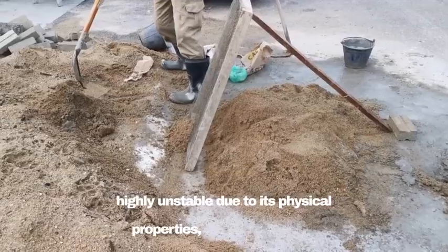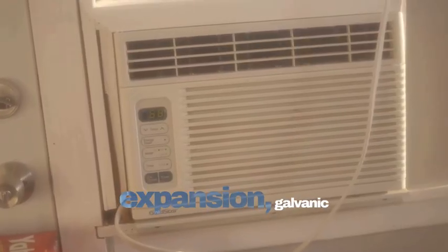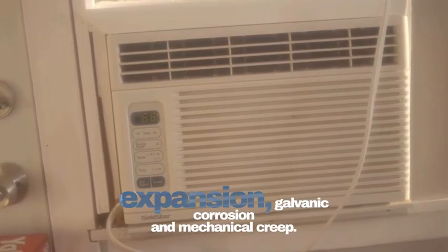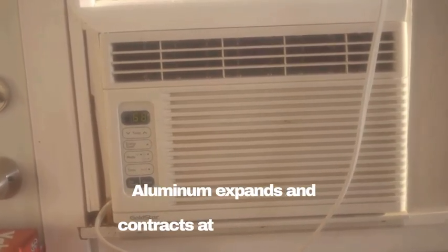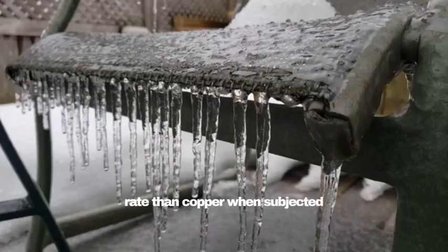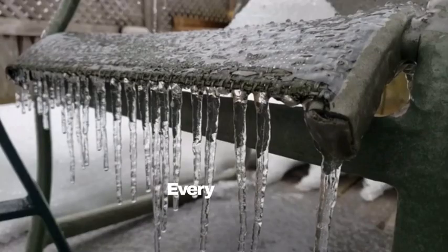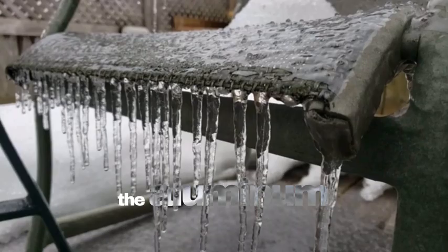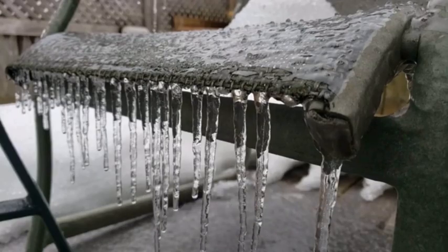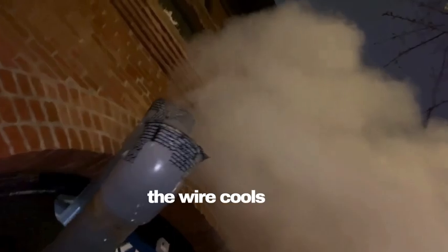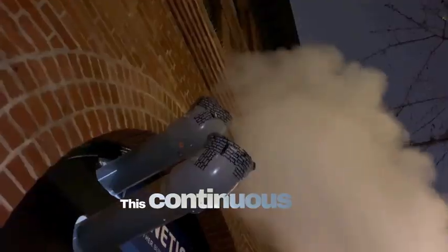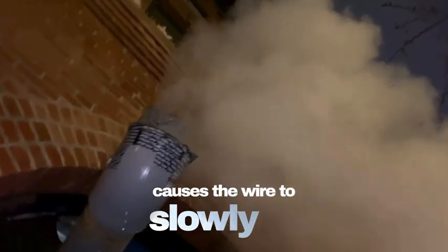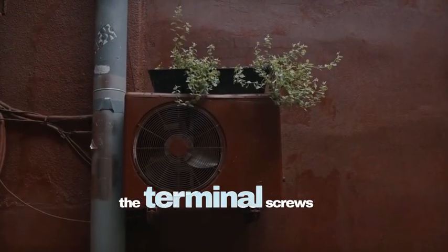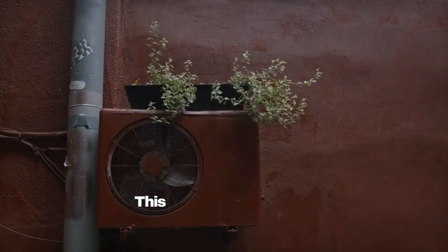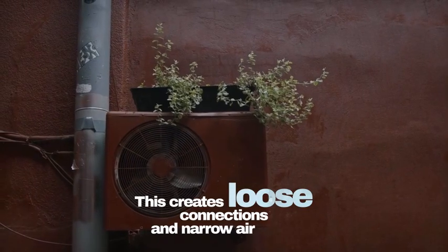its physical properties: thermal expansion, galvanic corrosion, and mechanical creep. Aluminum expands and contracts at a much higher rate than copper when subjected to electrical currents. Every time an appliance is turned on, the aluminum wire heats up and expands. When the appliance is turned off, the wire cools and contracts. This continuous cycle, known as thermal cycling or creep, causes the wire to slowly back out from under the terminal screws of standard outlets and switches. This creates loose connections and narrow air gaps.